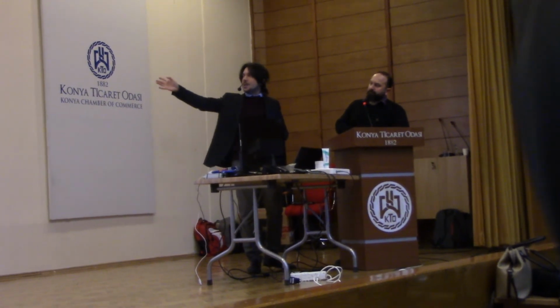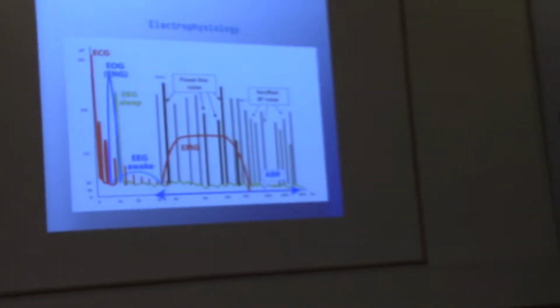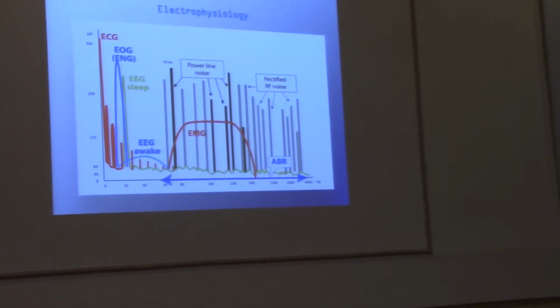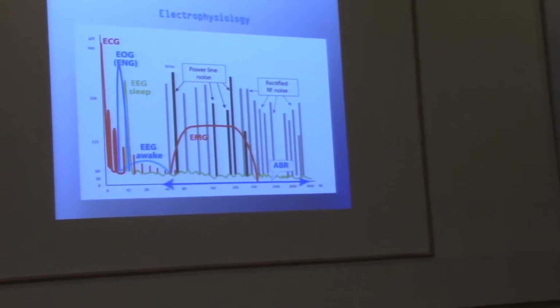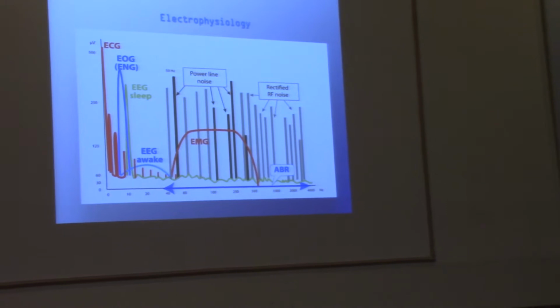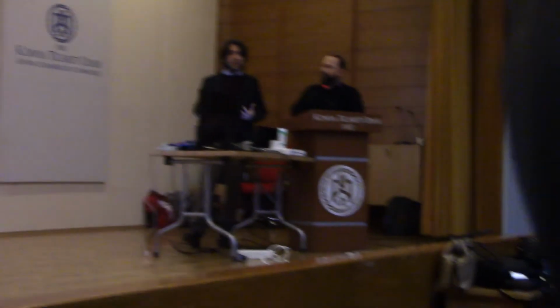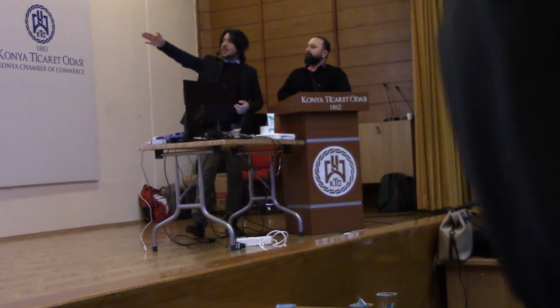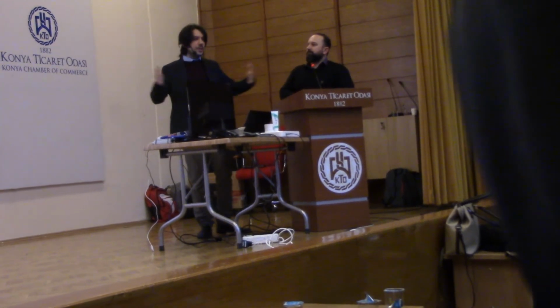This is a summary of all the interferences or all the signals that can be in your environment, okay? Some of them are created by the patient itself, and some of them come from the environment.